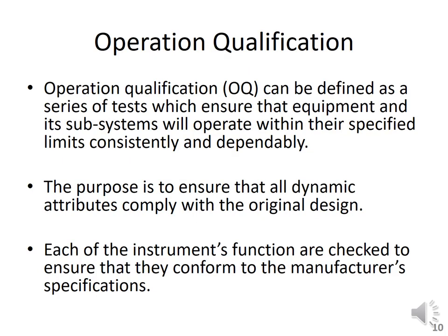The next is operational qualification. Operational qualification can be defined as a series of tests which ensure that equipment and its subsystems will operate within their specified limits consistently and dependably. Right? So you can say that the operational qualification protocol is a collection of test cases used to verify the proper functioning of a system, right?